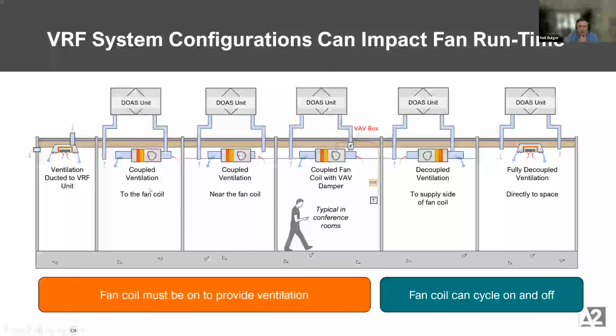Functionally, we've seen these other configurations also that we kind of call coupled ventilation. Air is supplied to the back of the fan coil or near it in a plenum. And again, that fan, to keep the ventilation in the space, has to stay on at some level of operation to make sure fresh air comes in. The really efficient ones are where we can configure fresh air to come in regardless of when that fan coil runs. So allowing that fan coil to be configured so it could cycle all the way off, or at least to a really low speed. And that can be a challenge, right? You sometimes need to precondition the air so it doesn't get so cold in the winter or too hot in the summer. But the solutions that can do that, you'll see, really can benefit from changing their fan energy equation. So how it's configured makes a big difference.